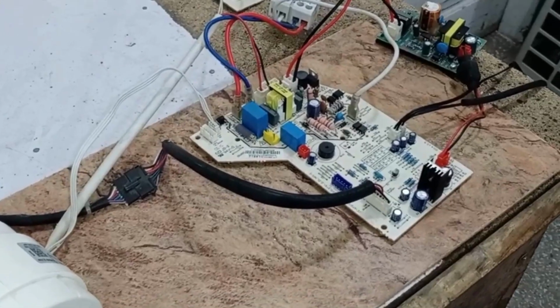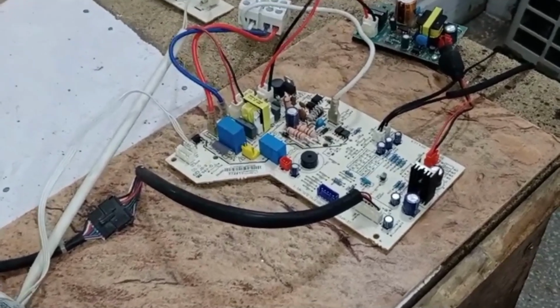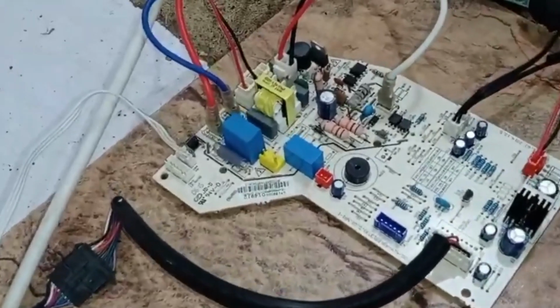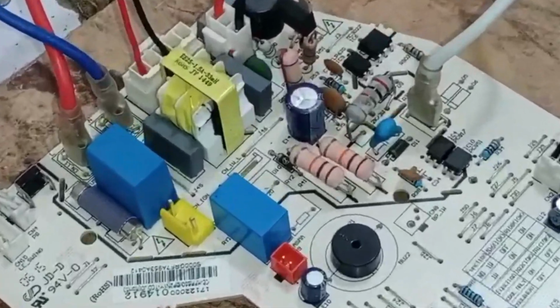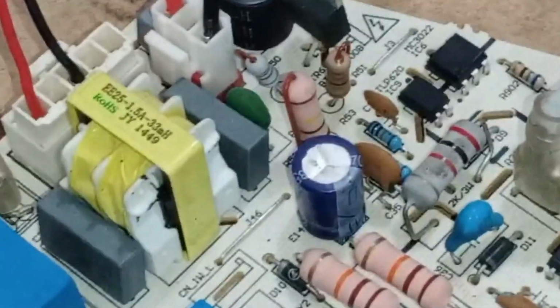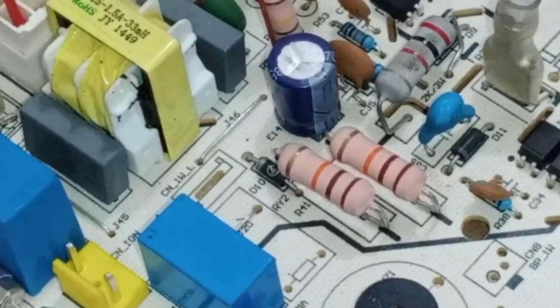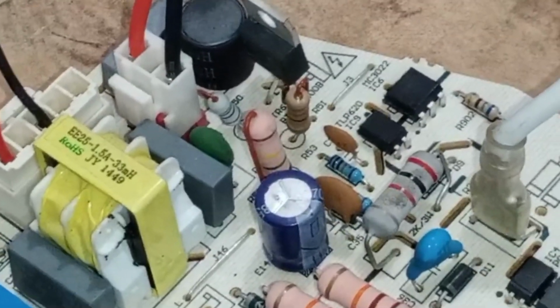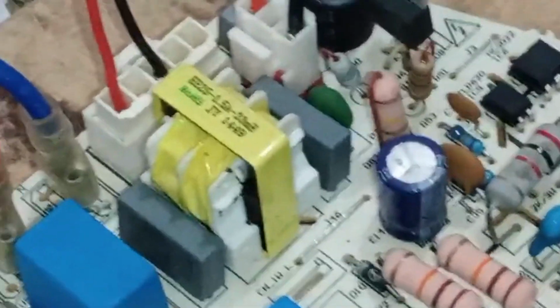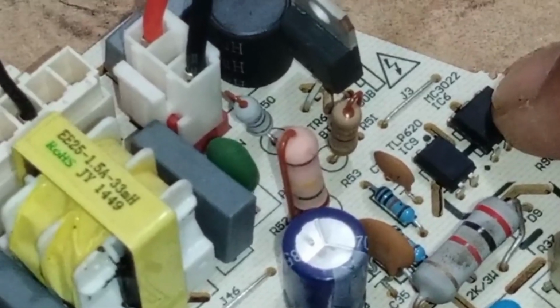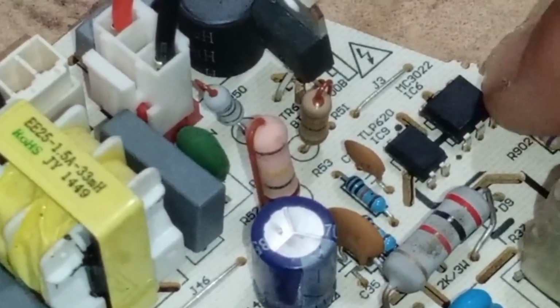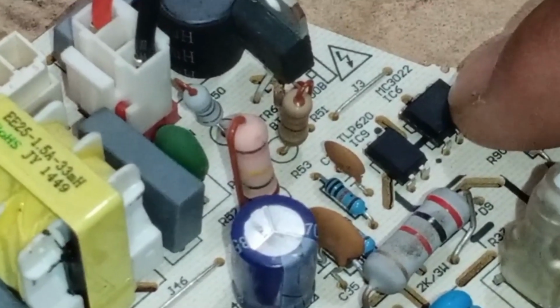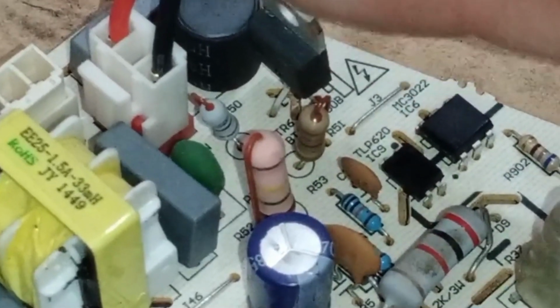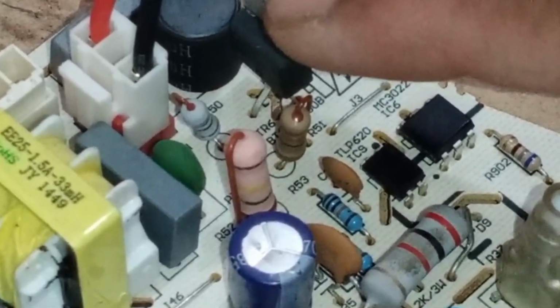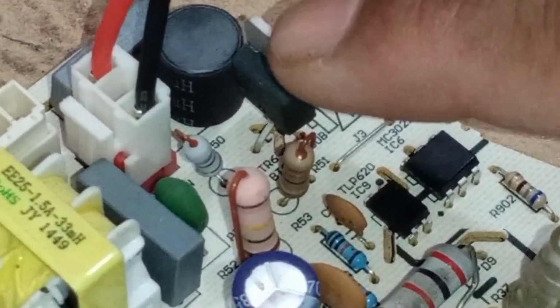Talking further about the E3 error, it could also be due to a PCB fault. There are certain components on the PCB that, if damaged, can cause this problem and trigger the E3 error. If the microcontroller is functioning properly and the voltages are being output correctly, you should then check the MC3022. This component, also known as a photocoupler, might be faulty. It drives low voltages and then passes them to the triac, which controls the motor's speed. If the photocoupler is damaged, it can lead to issues.